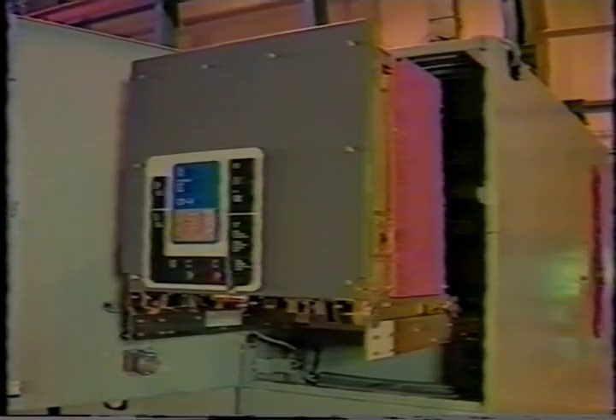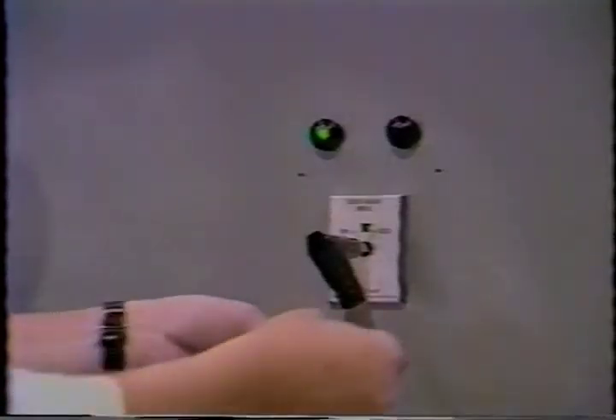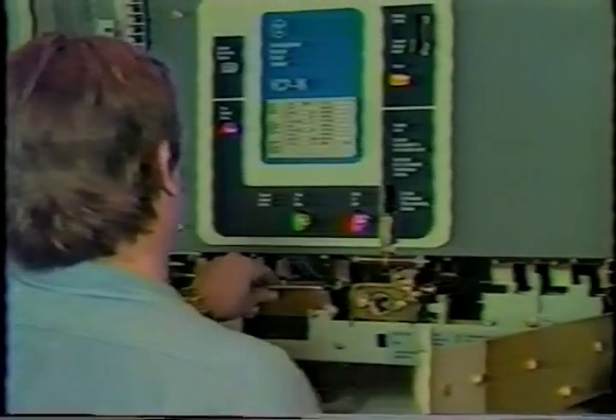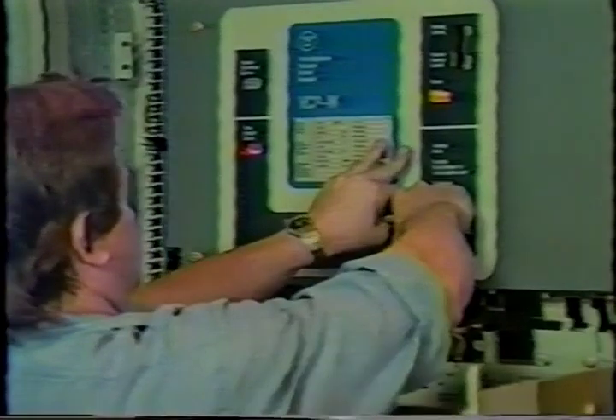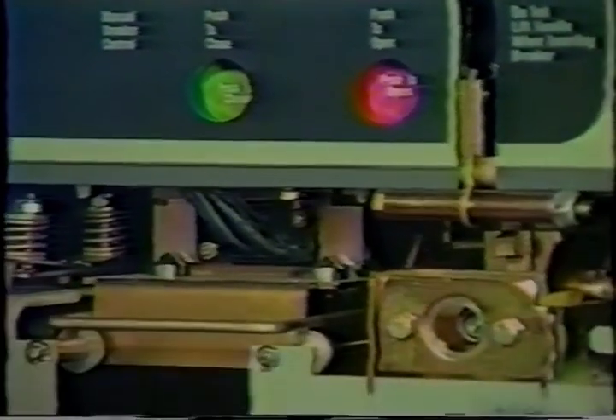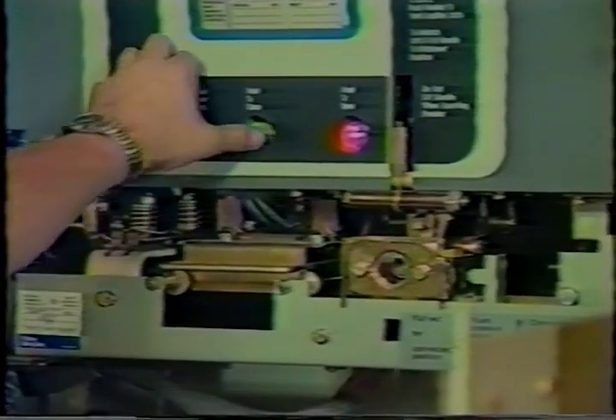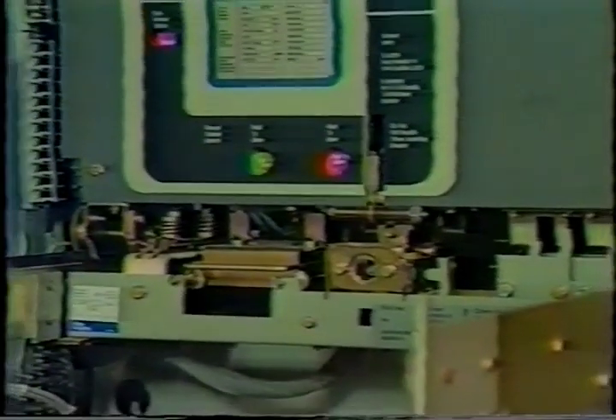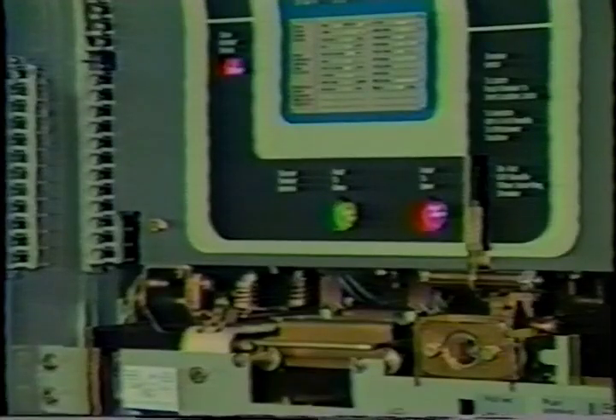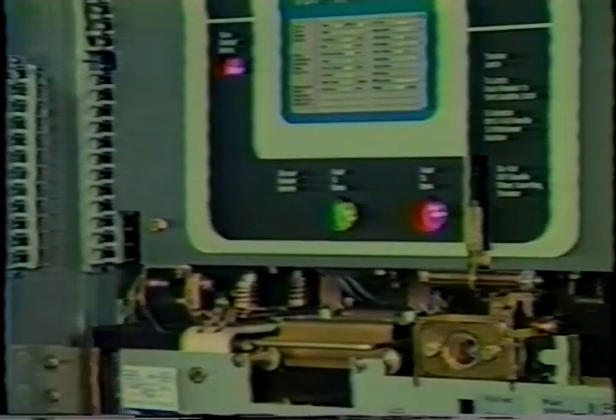These breakers are designed with safety in mind. The following procedures will verify the correct operation of the various safety interlocks provided for these breakers. Make certain the primary circuit is not energized during these tests. Close the breaker in the test position. The maintenance interlock may be checked by attempting to move the closed and charged breaker from the test to the withdrawn positions. The breaker will trip, close, and trip again to discharge the stored energy mechanism. Return the breaker to the test position and close it. The levering interlock will trip a closed breaker when an attempt is made to move it to the connected position.